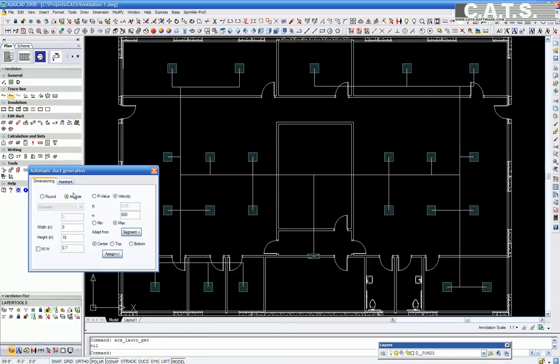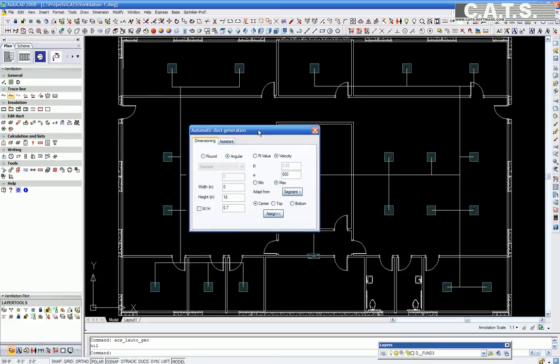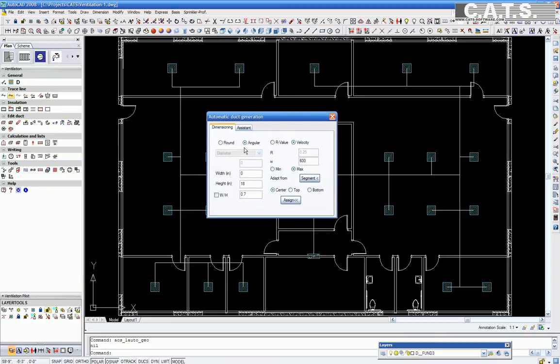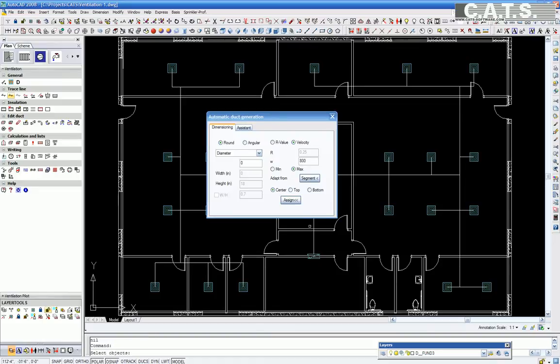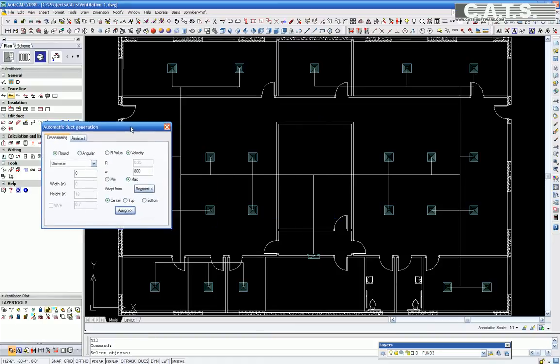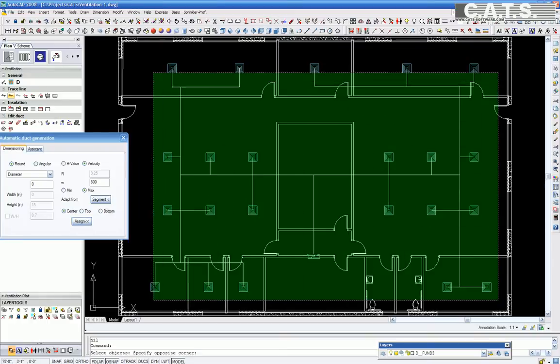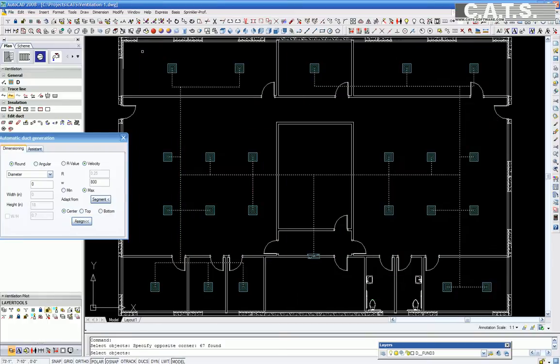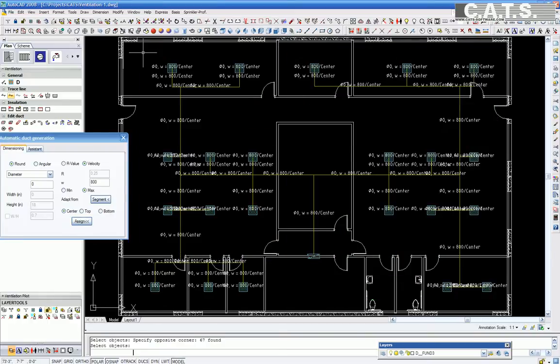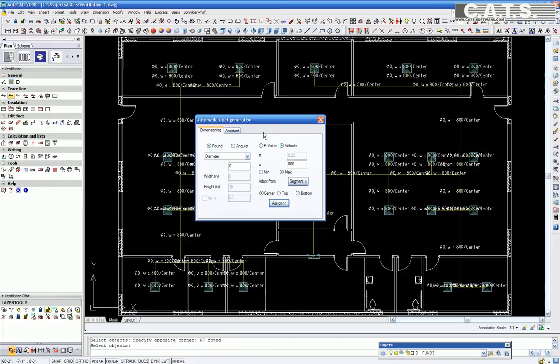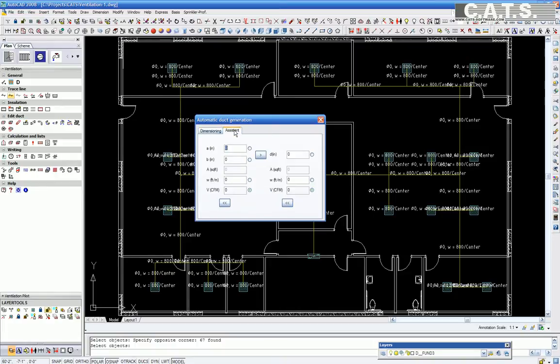Under Dimensioning, we will select Round and decide to let the software calculate the sizing of our round duct according to our velocity of 800 feet per minute. We change 600 to 800 in the window. We are now going to assign the round duct work by highlighting the entire duct system. The software recognizes our center line. Now all the information is displayed in yellow as the round duct system.